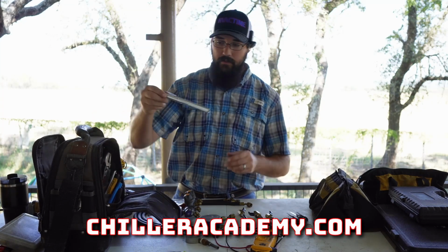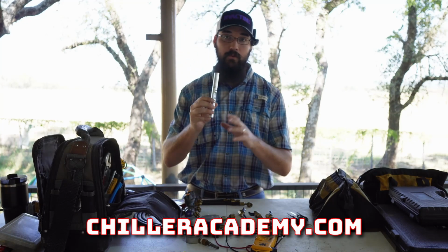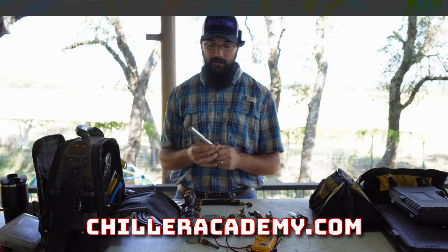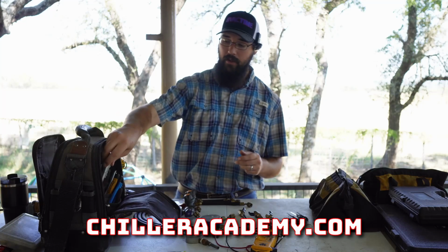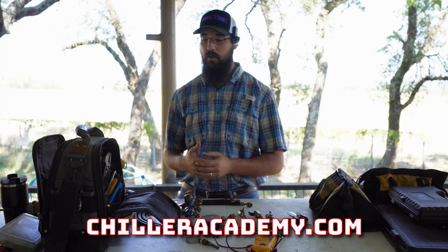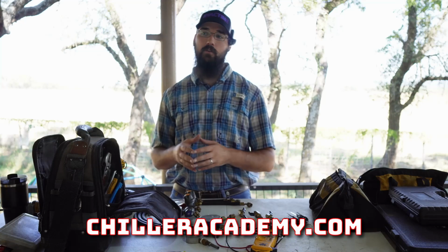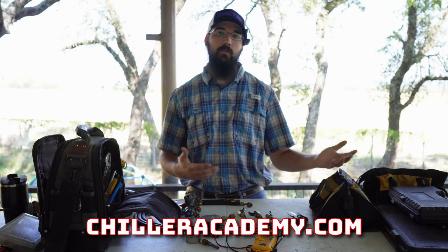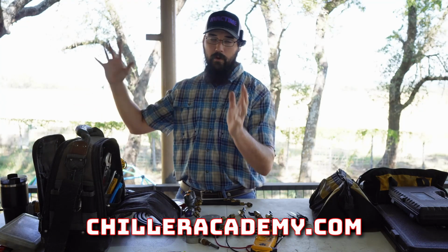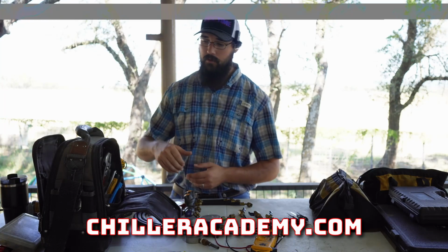Okay, moving through the bag, psychrometer. This should be a really key tool. Should already be a part of your bag. If you don't carry a psychrometer, this is just a little pin style that sits in your pocket. It's not that expensive. These are things to have, especially when we start doing any kind of cooling tower troubleshooting and work. Understanding what your approach is and your wet bulb is critical, right? So from a chiller world, we don't get away from psychrometrics. When we start dealing with cooling towers, we're actively engaged in a psychrometric chart there, and we need to understand what our wet bulb is so that we can properly troubleshoot.